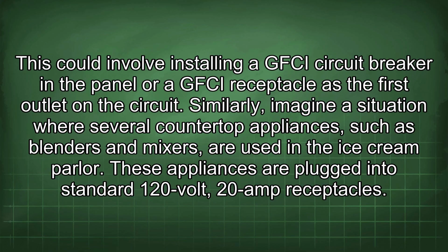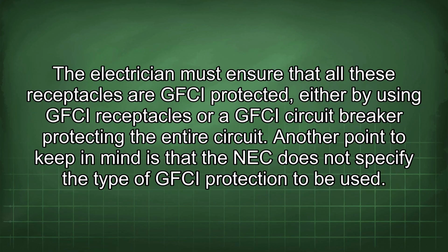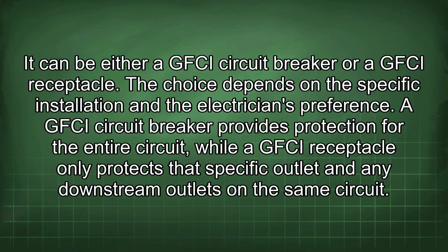the circuit. Similarly, imagine a situation where several countertop appliances, such as blenders and mixers, are used in the ice cream parlor. These appliances are plugged into standard 120-volt, 20 amp receptacles. The electrician must ensure that all these receptacles are GFCI protected, either by using GFCI receptacles or a GFCI circuit breaker protecting the entire circuit. Another point to keep in mind is that the NEC does not specify the type of GFCI protection to be used. It can be either a GFCI circuit breaker or a GFCI receptacle. The choice depends on the specific installation and the electrician's preference.